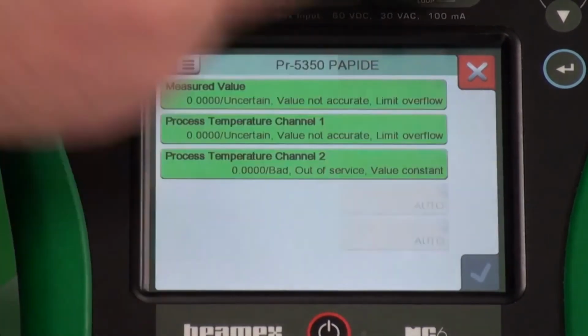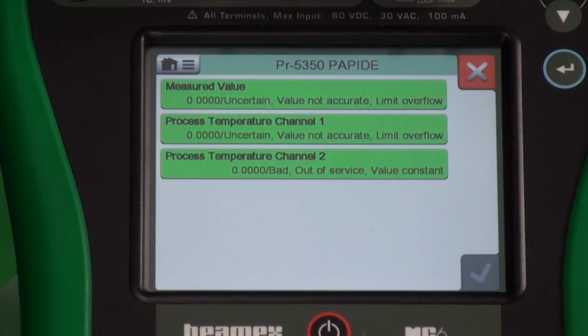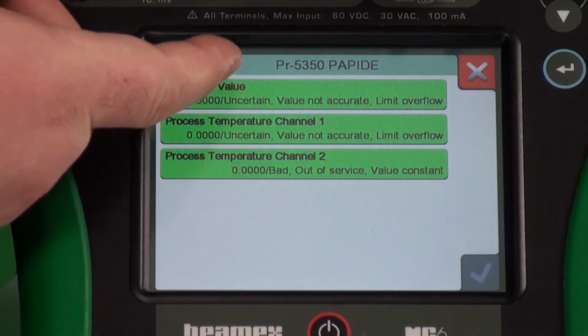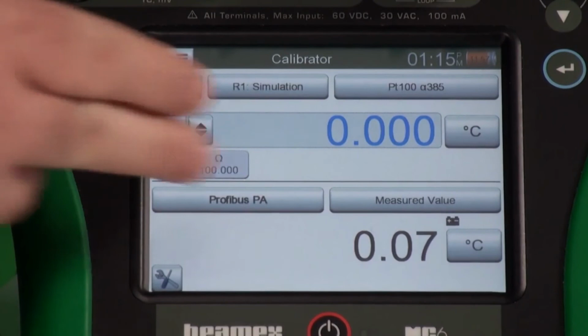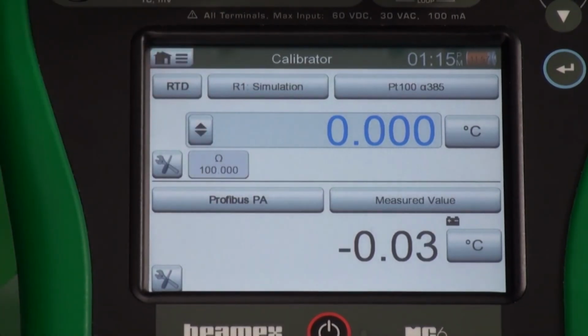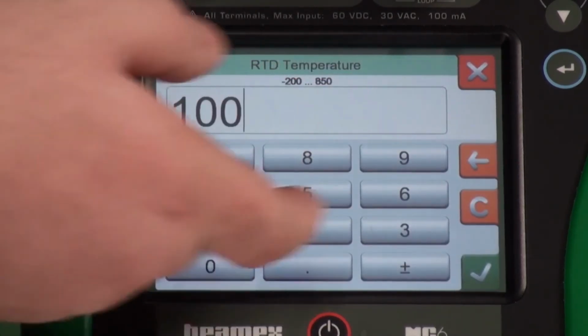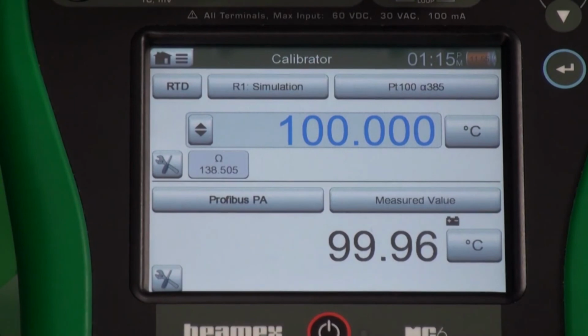Now if we wanted to, we could hit the menu button and do show measurable variables, and that shows you anything that can be measured. Let's go to our primary. Here's our actual output. Let's get rid of some of these decimals. So this is our output. We're feeding at 0 degrees Celsius. If we change this, we see a direct relationship with our output of the transmitter. So we are communicating with this via Profibus.